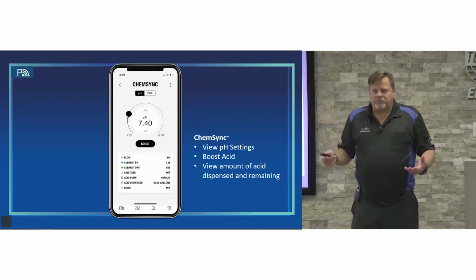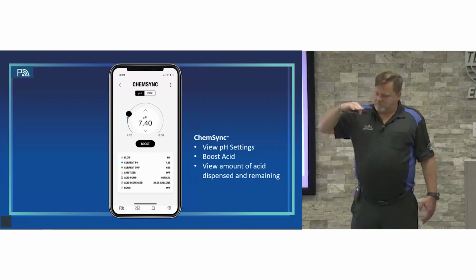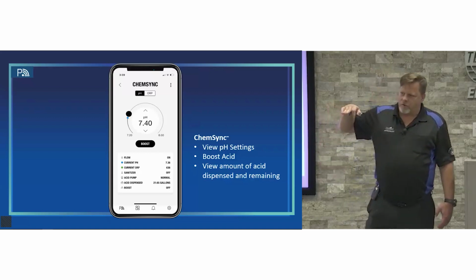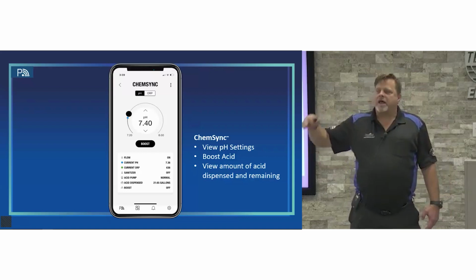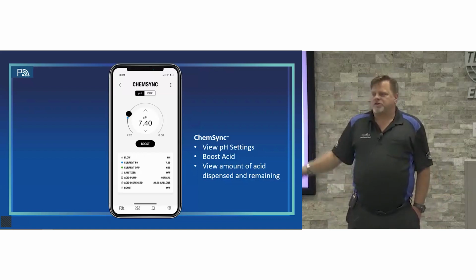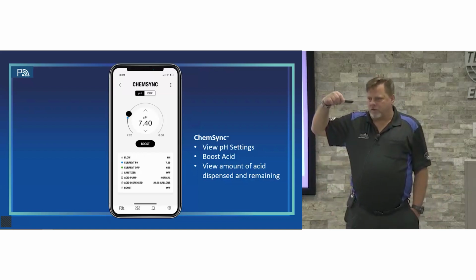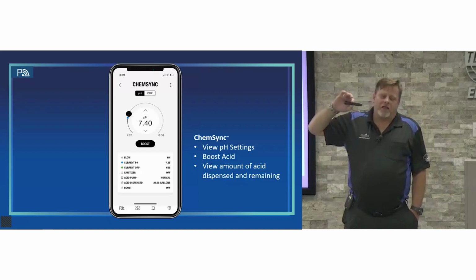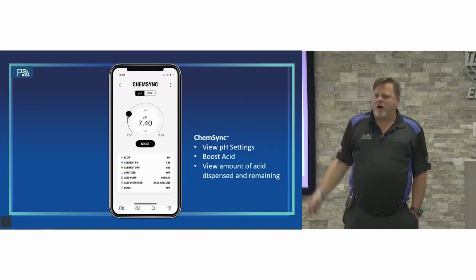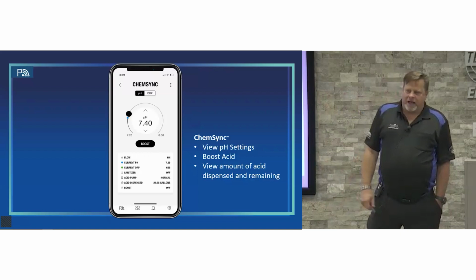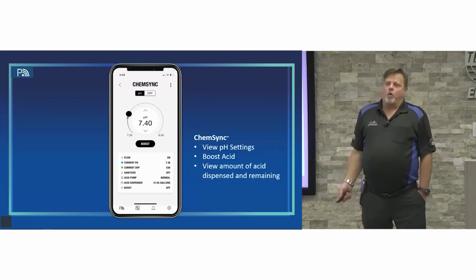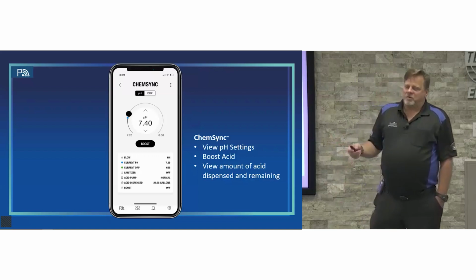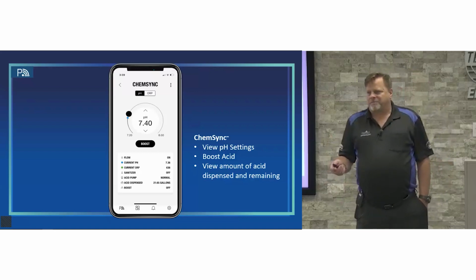And then basically let it run for 24 hours. Then check the chlorine level after 24 hours, make sure it's still in the parameters that you want, and then set the ORP. As long as you're maintaining after 24 hours the chlorine level that you want to maintain that pool at, that's a good, roundabout number to set your ORP set point at. Like I said, just understand this: if your water chemistry changes, that number isn't going to be the magic number for it.